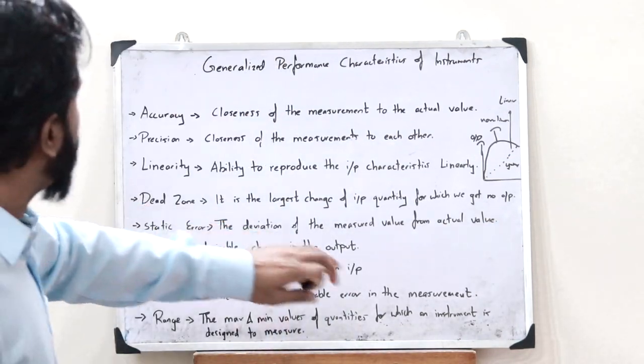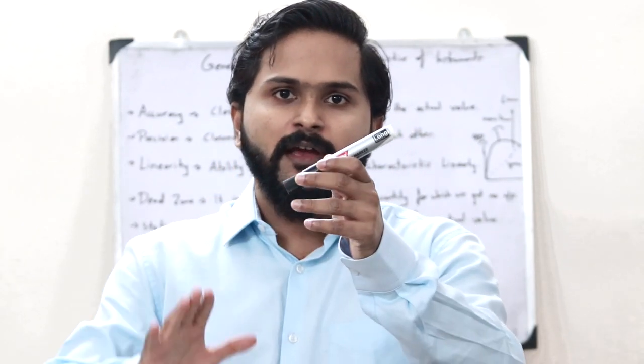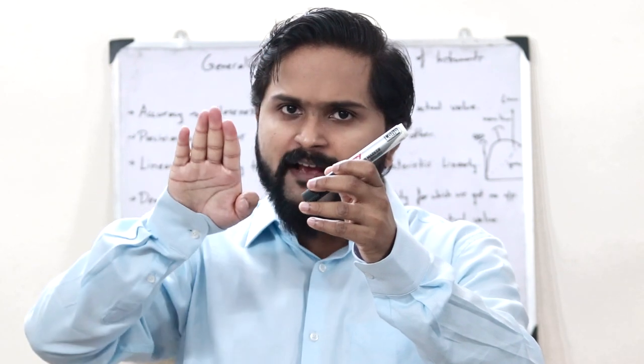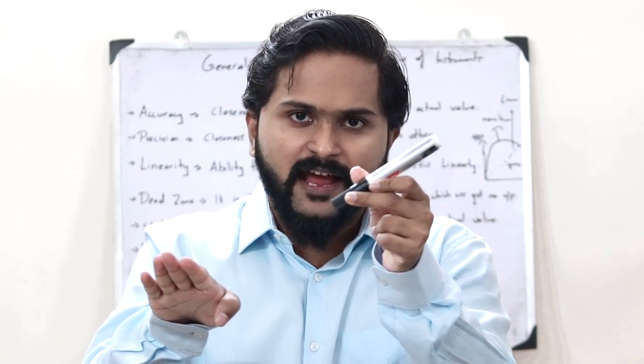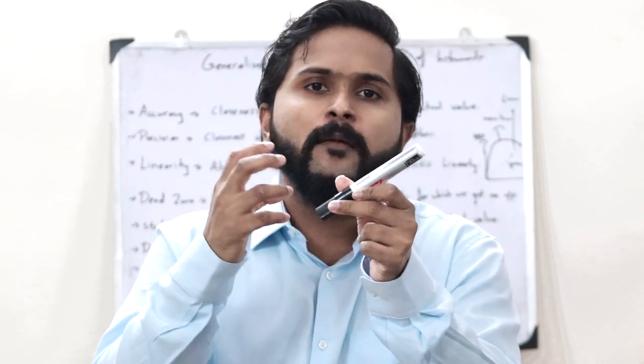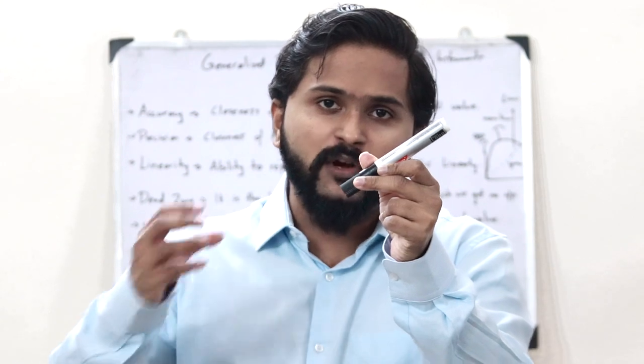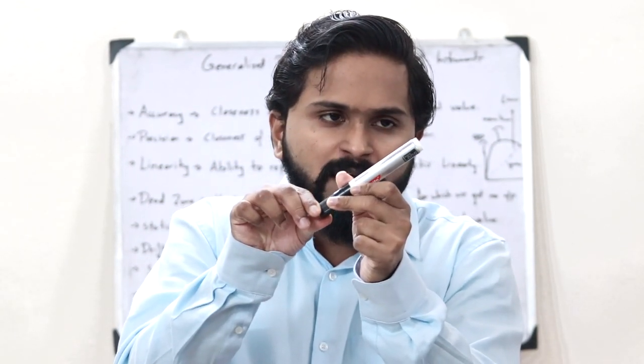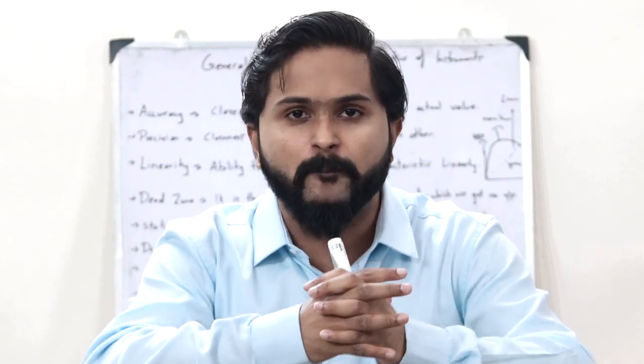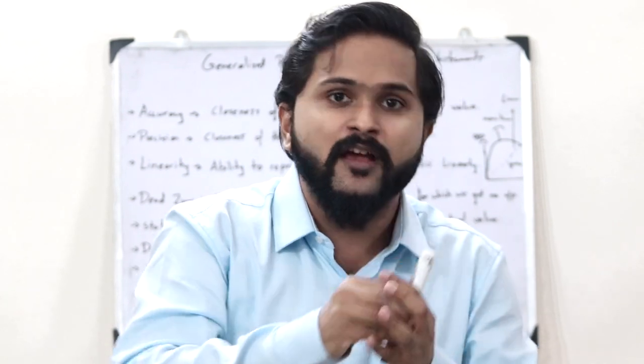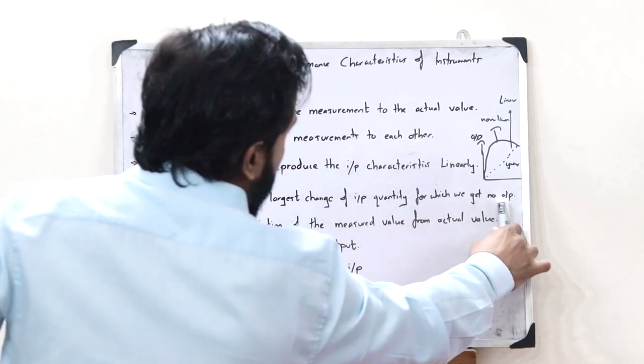Next we have dead zone, which is a very interesting parameter. Imagine the speedometer of your car showing 60 kilometers per hour. If you accelerate and you can feel the car increasing its speed, but the speedometer still shows 60 km/h — only after the car crosses a certain speed does the reading change. That particular speed range for which we see no change in the speedometer reading is the dead zone. It is defined as the largest change of the input quantity for which we get no output.